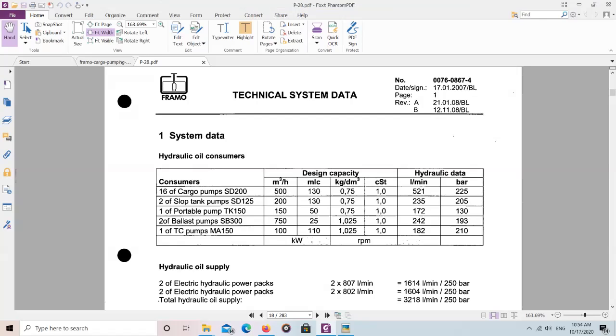The system line pressure is controlled and kept up to around 180 bar. The design criteria for the electric motors: two hydraulic electric power packs of 800 litres per minute capacity each — 1600 litres per minute combined — for 250 bar. That is the design capacity of the motors.